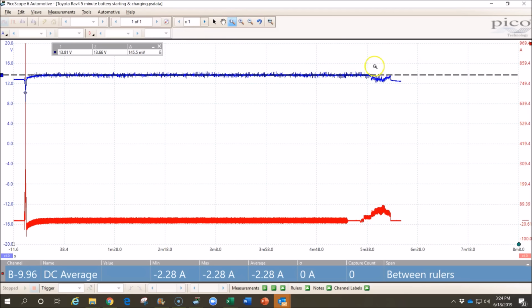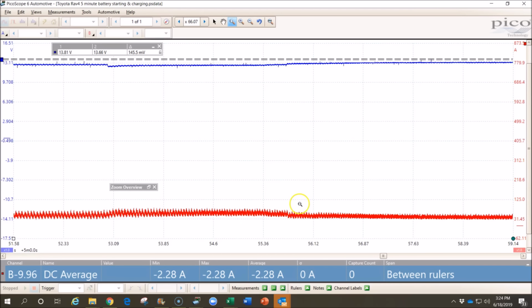So let's zoom in on this section right here. This is where we turned the loads on, and you'll see the current rose and the voltage dropped. But the voltage should be able to, especially when we raise the RPM up to about 1500 RPM, maintain or regulate itself between 13.5 and 15 volts still.